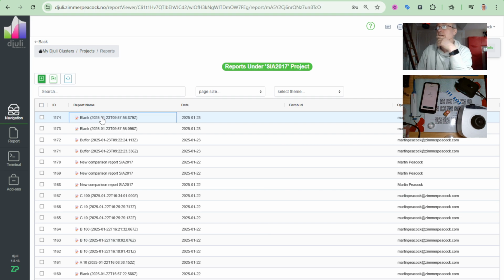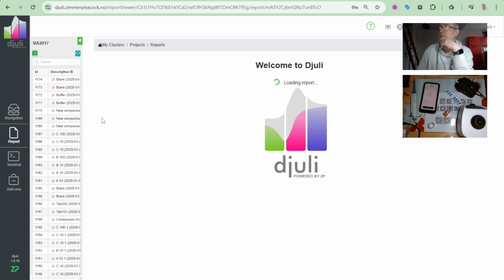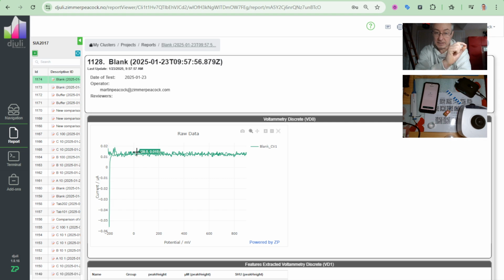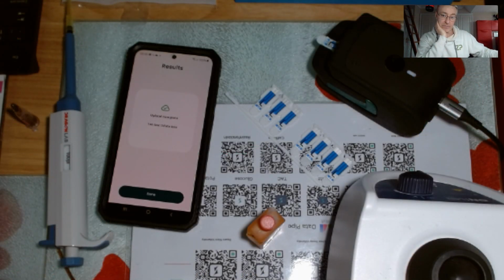So I'll go up there and check on myself. I was like, oh, that's a bit weird. Let's have a quick look what's going on here. Well, that's weird. Now this time round the client hasn't done this, but look at this. I did this on purpose, and I just want to give people a heads up so they don't do this. But I have noticed in the past this particular client has done this. I put the sensor in there, but I didn't close it. The client hasn't done this this time, but I just want to give people a heads up that you may do this when you see your data like that.